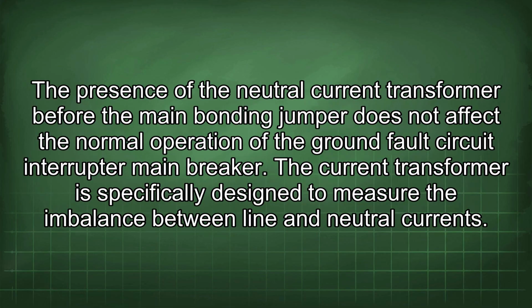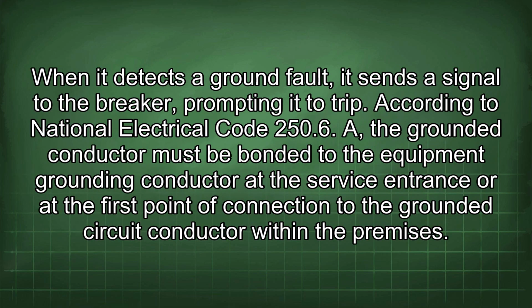The presence of the neutral current transformer before the main bonding jumper does not affect the normal operation of the ground fault circuit interrupter main breaker. The current transformer is specifically designed to measure the imbalance between line and neutral currents. When it detects a ground fault, it sends a signal to the breaker, prompting it to trip.